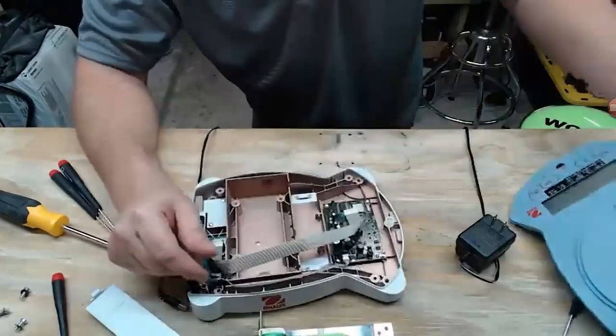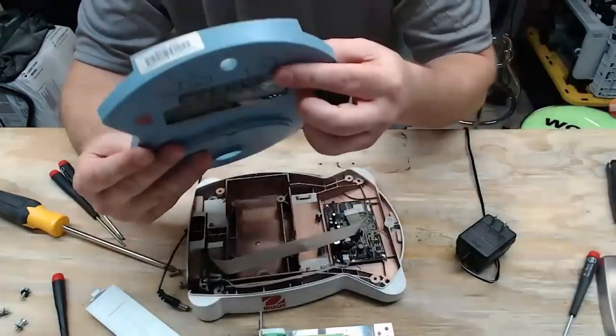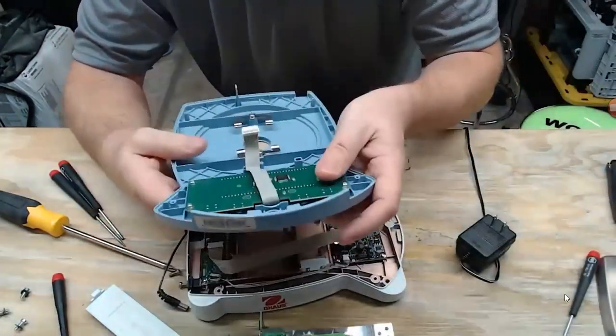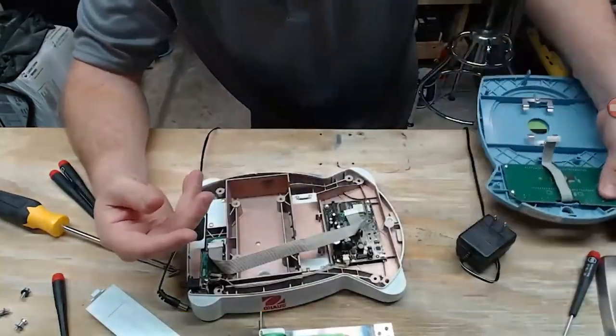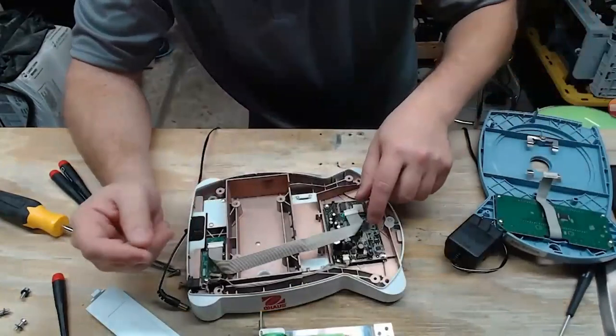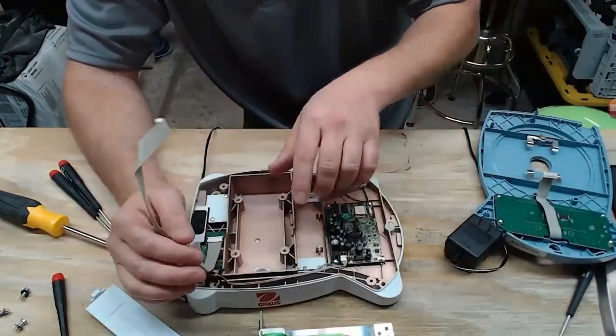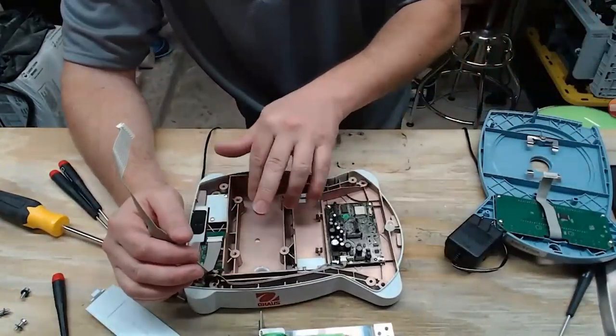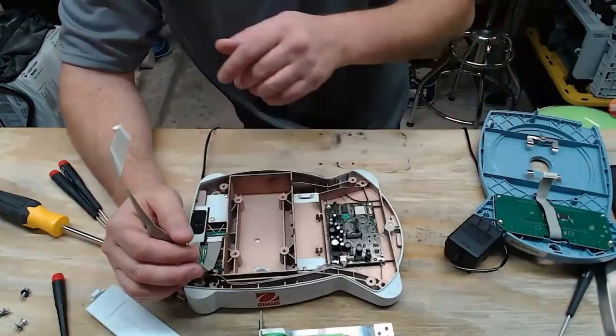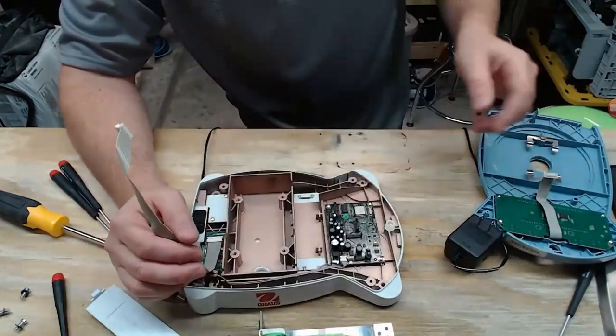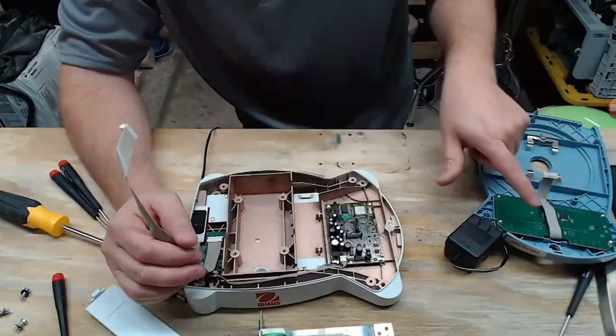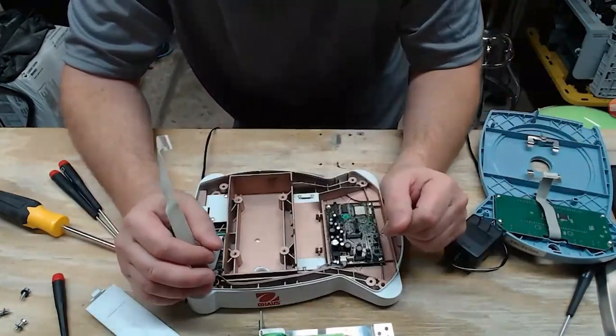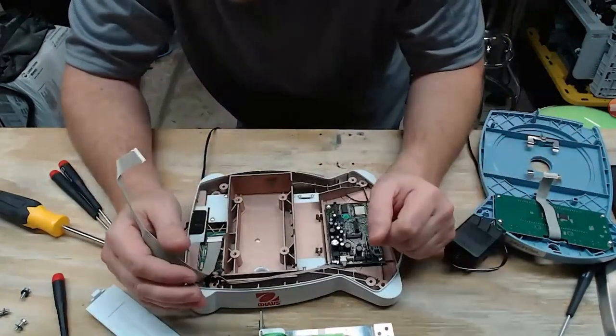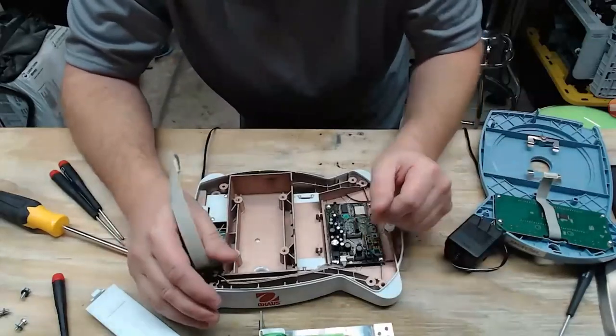digital scale. Nothing too fancy. Up here, you got your membrane buttons, which go to your controller for the membrane buttons. And all they do is relay back to your processor. So the processor is doing the comparison of your load cell on the Wheatstone bridge, and it's also taking your commands from the membrane buttons. Pretty simple. Nothing major there.